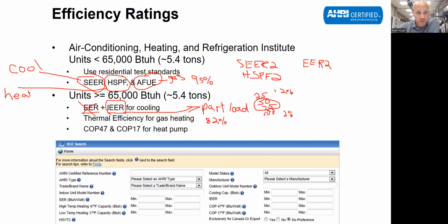If you have a heat pump, you don't get an HSPF number. You get COP, coefficient of performance, at 47 and at 17 degrees. And we talked about those a little bit last week too. But basically, they run it on a 47-degree day, see how efficient it is. Run it on a 17-degree day, see how efficient it is. By the way, I didn't mention it, but residential heat pumps now, in addition to HSPF, also have a COP5, which means coefficient of performance on a 5-degree day for the small ones. So it's kind of weird.